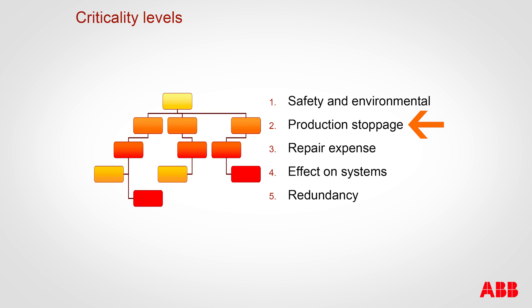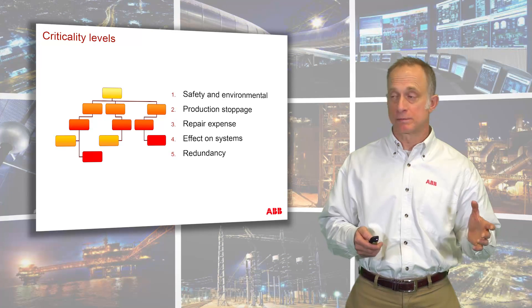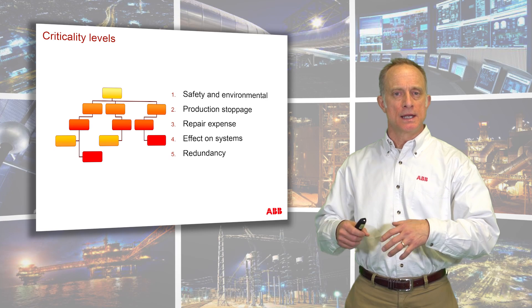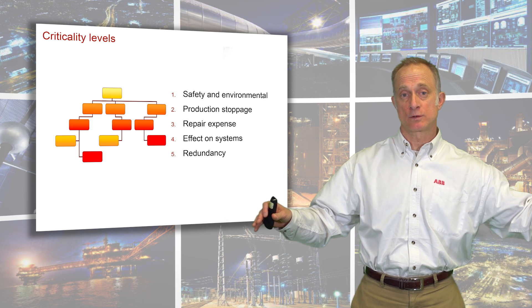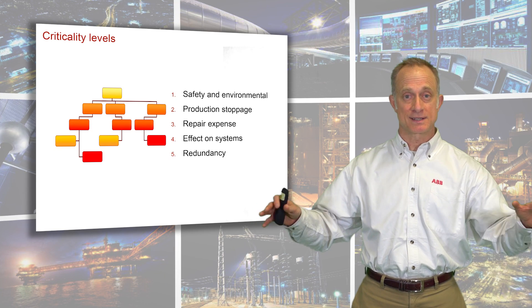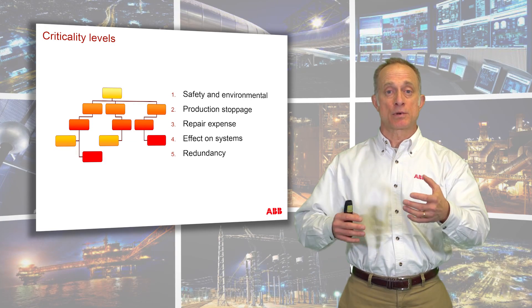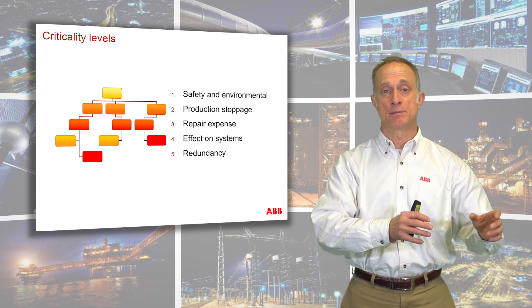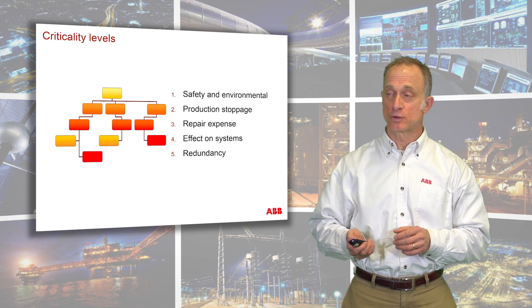The next consideration is production stoppage — if you're not making product, you're not making money. The third is maintenance expense — how costly is it to repair a certain piece of equipment? The fourth is the effect on the systems: a system is a collection of equipment, so what is the ripple effect if something breaks here on other pieces of equipment? And fifth, redundancy — does this process have redundant features so that if it fails in one area it picks up in another? If it's lacking redundancy, then it could be a higher level of criticality.